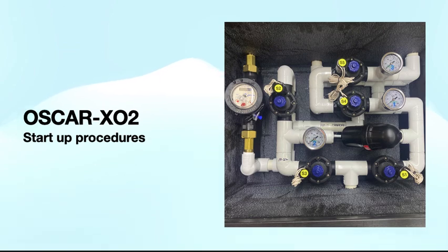This headworks is all going to be the same, and the diagnosis, what we call the startup procedures, are going to help us make sure everything has been wired correctly right after initial installation. If for any reason you have to go back out to look at something, if there is an issue, because we have expected pressures on these pressure gauges and expected flows going out to the Oscar, when something is off, this will help us pinpoint where the issue might be. So these startup procedures need to be done at the conclusion of every installation.